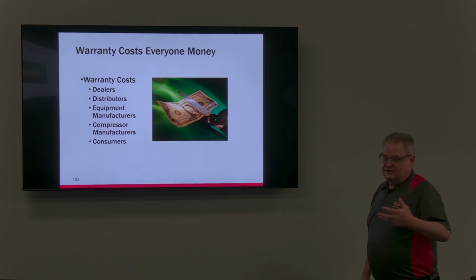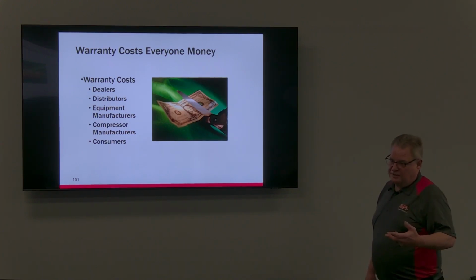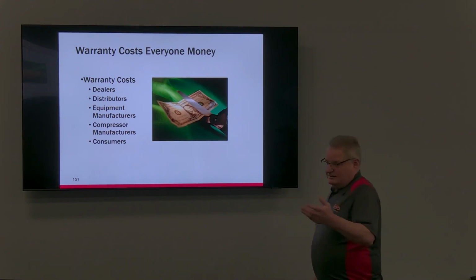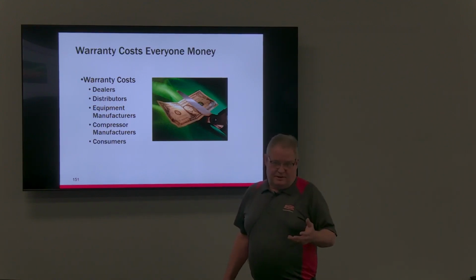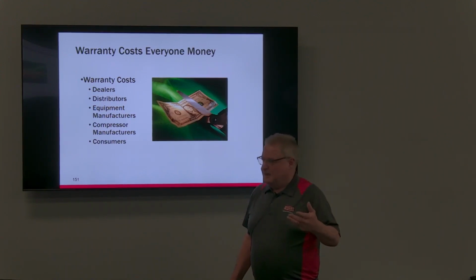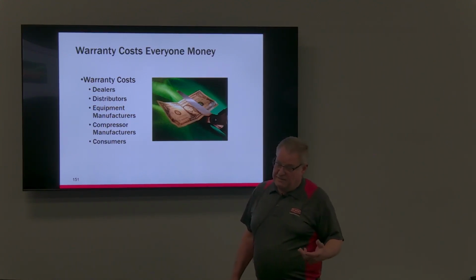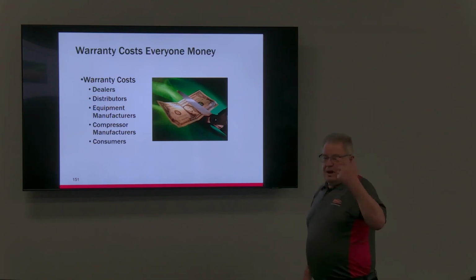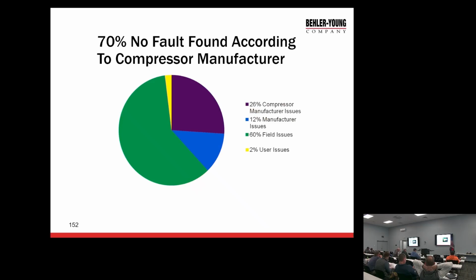Obviously, not doing things correctly causes us lots of problems. That green is real obvious because we have no filter dryers, so you see it. I've got several of those pictures now where that's happening. So proper evacuation: change the vacuum pump oil first. Run nitrogen when we braze.